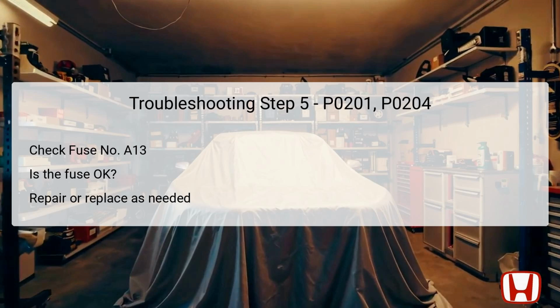If the fuse is operative and shows no signs of damage, you will need to repair any breaks in the +B IGP wire between this fuse and the injector relay. However, if the fuse is indeed blown, the fuse must be replaced and the short condition causing the break must be resolved to restore normal function.